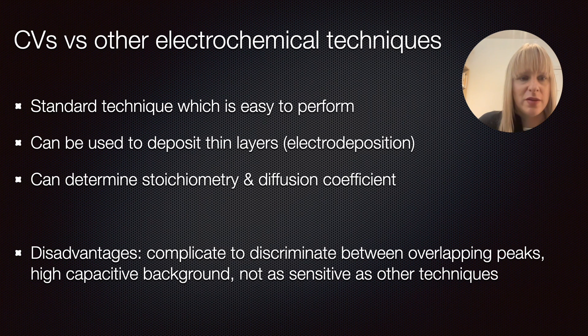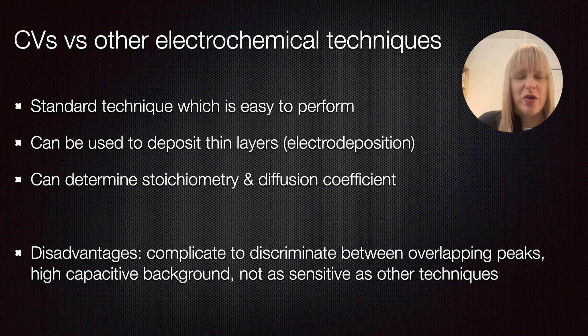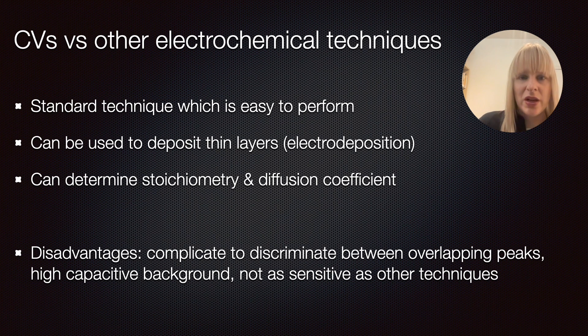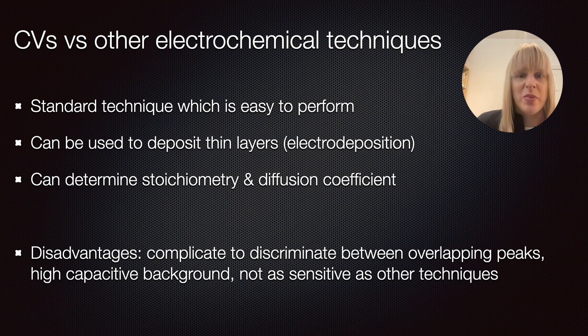The disadvantages of the system are that particularly if you have multiple peaks, it can be very complicated to discriminate between them, making it quite challenging. Compared to techniques like differential pulse voltammetry or square wave voltammetry, CV is not as sensitive, so for very specific sensing applications it might only be good as a starting point — it's not something commonly used in commercial sensors. Also, if you do multiple cycles you have to scan forwards and backwards, which can be more time consuming, and in most cases you want the result as soon as possible. Furthermore, going towards higher potentials can give you a high capacitive background, meaning some peaks might disappear into that background.